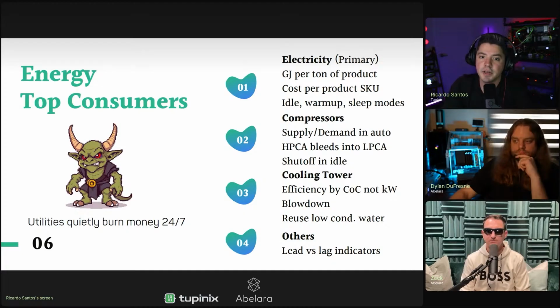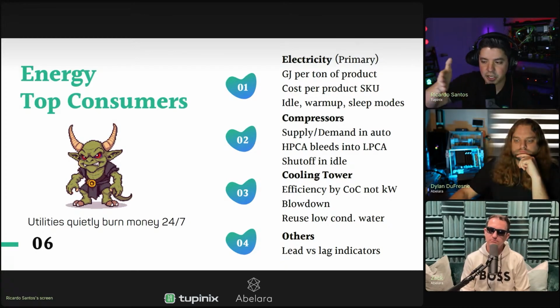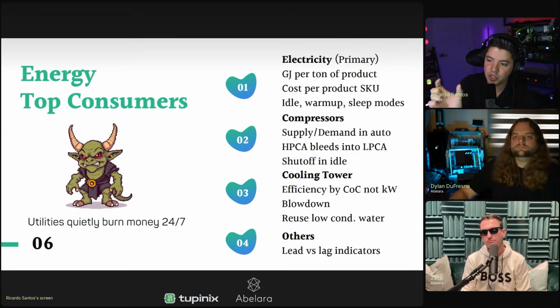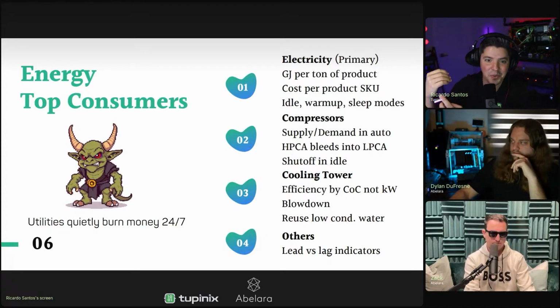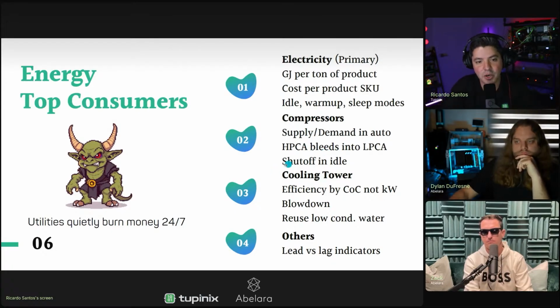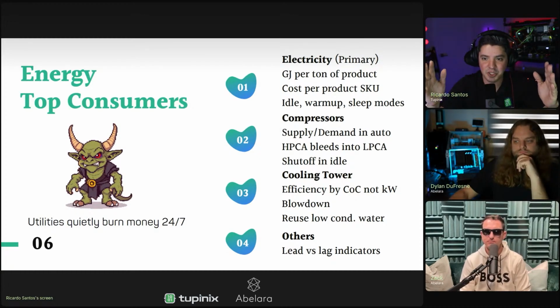Yeah, we do a lot of that. Once I started learning about regen — because we do these hot water sets and pasteurization — this is very cool. You heat it up, so you have a plate heat exchanger, for example. One section is heat, the other is cool, and the other is regen, because you can cool down while preheating with the preheated water that already passed through. You know what I mean? It's called the regen section of the plate heat exchanger, which I've always found fascinating, because you have like 20% heat, 30% cool, and then most of the plate heat exchanger is regen.